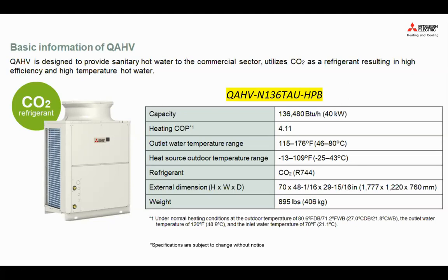And you may ask, well, what about the COP when outside temperature is maybe at 80 degrees Fahrenheit, right? If the inlet temperature is at 21 degrees C and the outlet at 65 degrees C, the COP can even reach up to 3.83. So it is still a very high performance equipment.